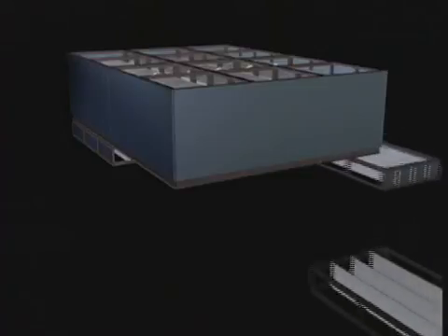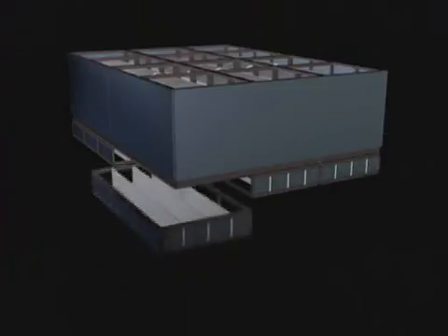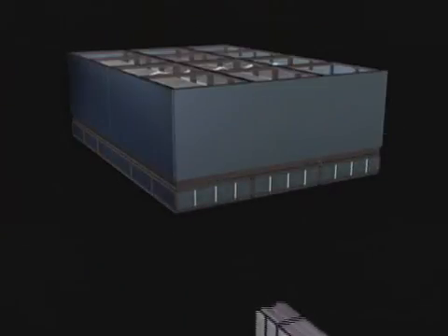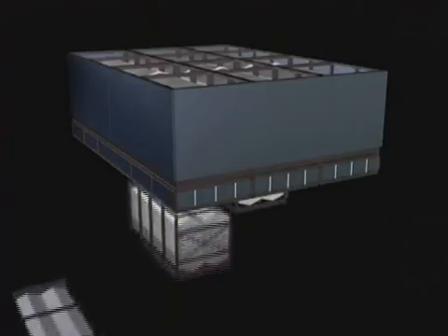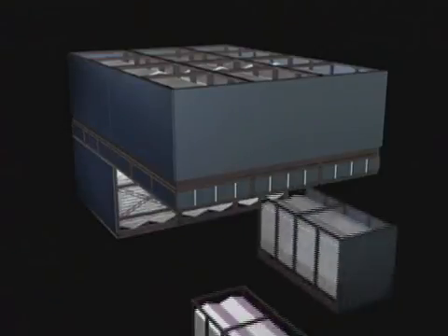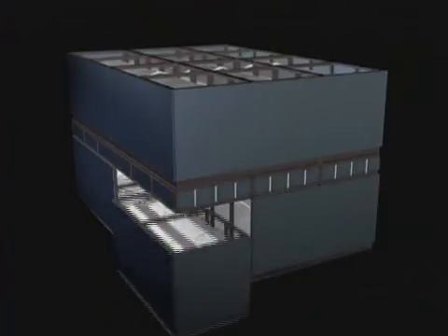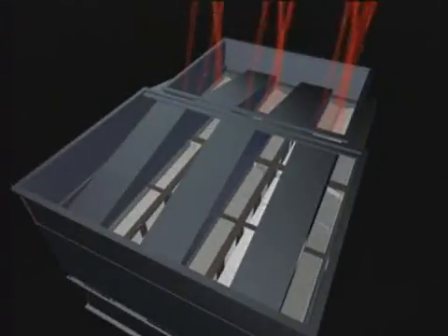On high efficiency applications, or when a separate cold end section is required, a second stage can be added to the exchanger. Frequently, the materials used in this second stage provide increased corrosion protection. The hot gases are ducted to each plate via the inlet and outlet distribution hoods to minimize any maldistribution problems.